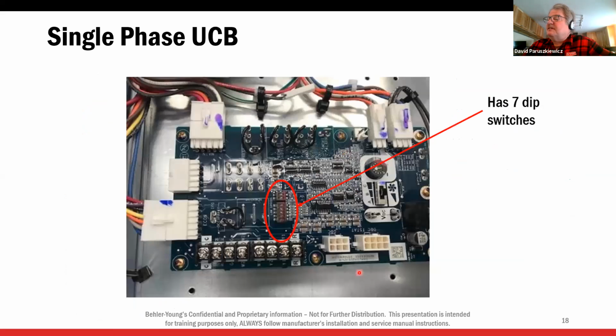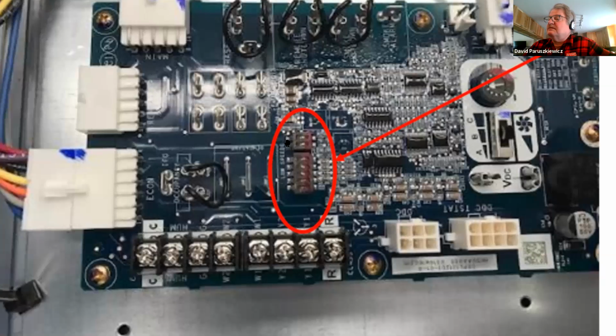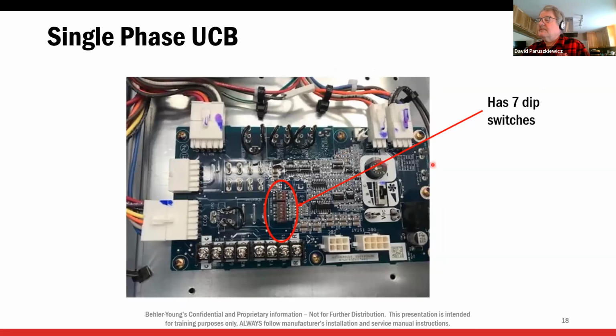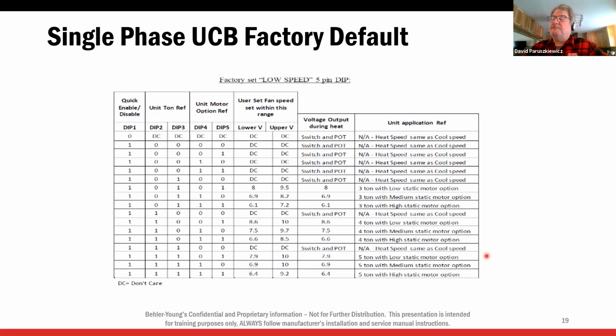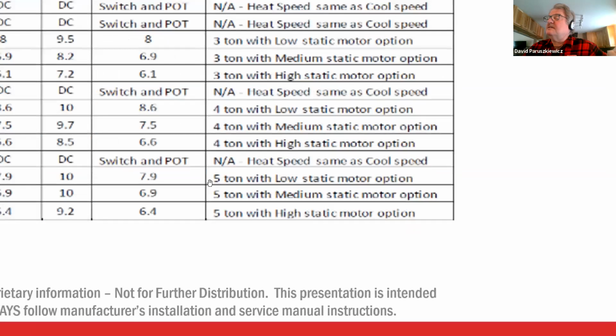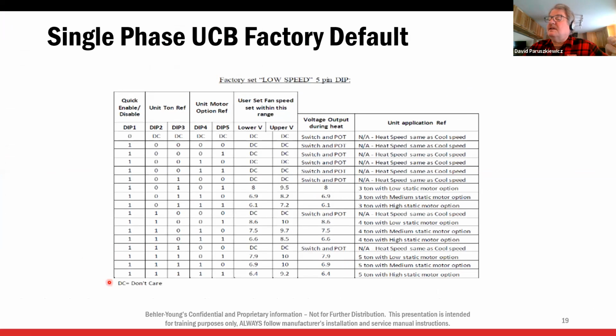Okay. There are some dip switches on the central terminal board. On the single phase unit, there are 7 dip switches here. You can see them here. And this little chart tells us what those switches are for. Basically, you're not going to mess with those switches. But if you replace that board for some reason, you need to make sure you put those switches back where they were. So in our example, we're dealing with a 5-ton unit. If I look down here at 5-ton, you can see 5-ton low static, 5-ton medium static, 5-ton high static. Those are 3 different units, and it tells you how those switches are set up. So those switches are specific to the unit. If you change that board, you need to put the switches back to where the old board was.